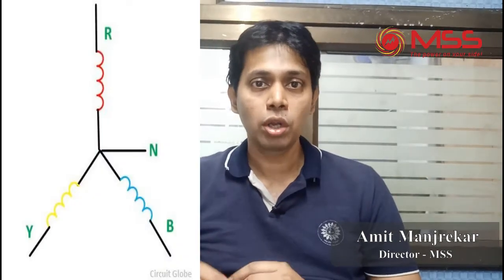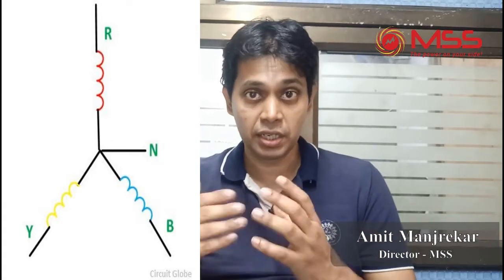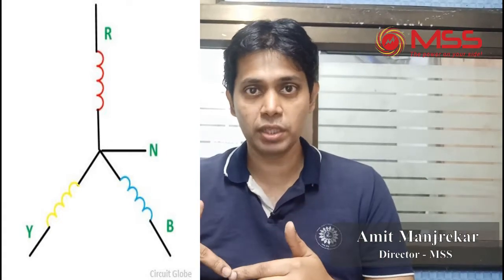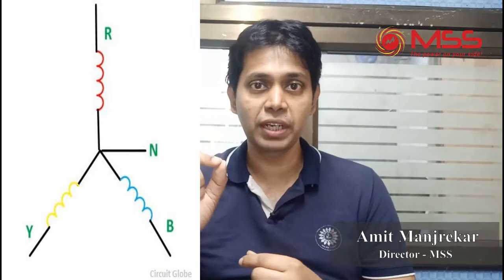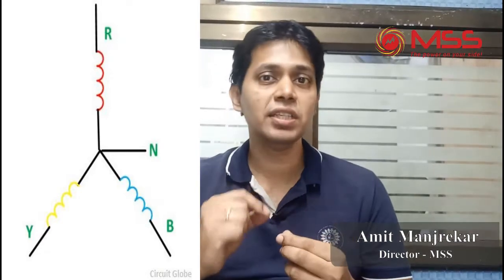This could have happened due to different reasons — it could be because of phase imbalance. In three-phase systems, the neutral point is where everything cancels out. In a star connection, all three phases are connected together, and the common point where all three phases meet is the neutral. Everything is supposed to cancel out at neutral, but if current is flowing more in one phase than the other, you can have phase imbalance, and that can cause a potential difference between neutral and earth.